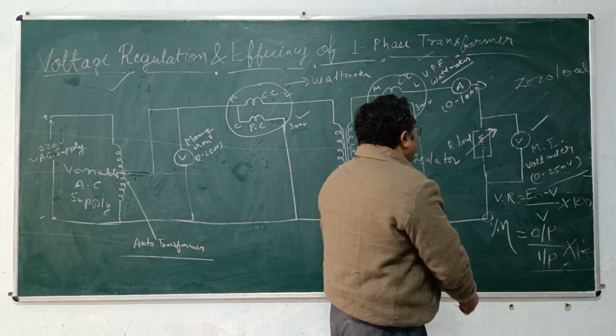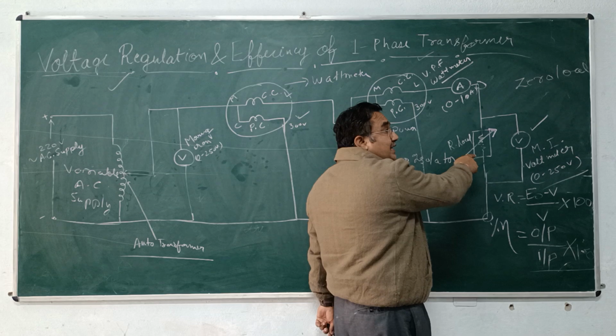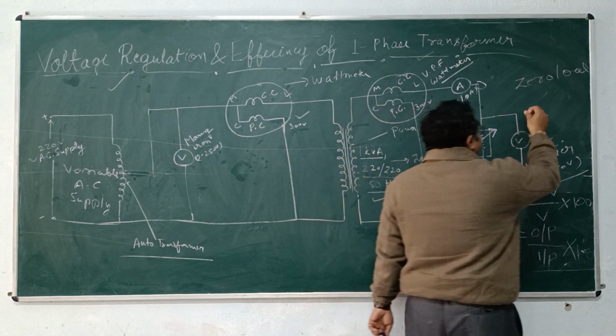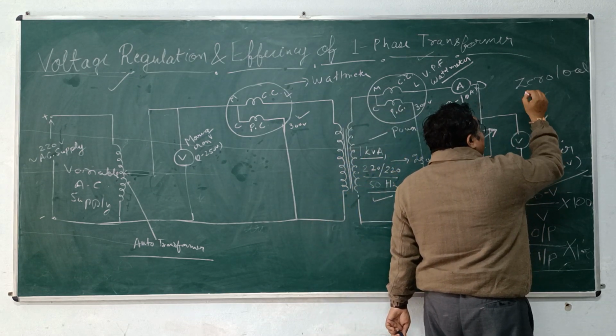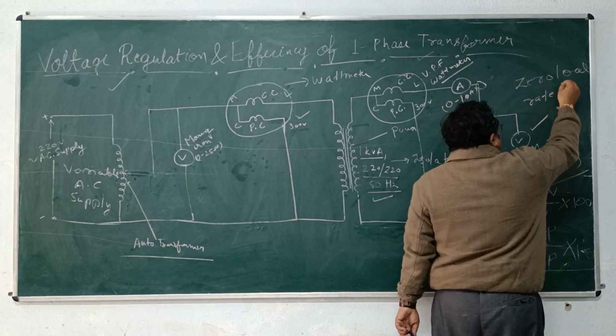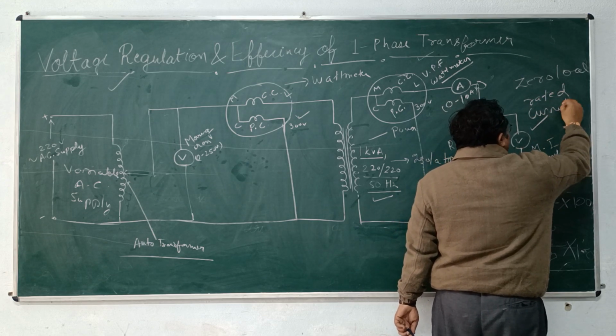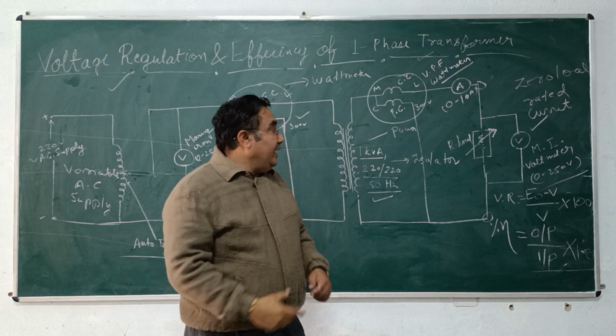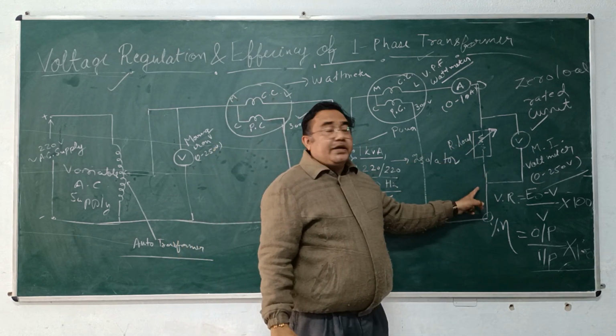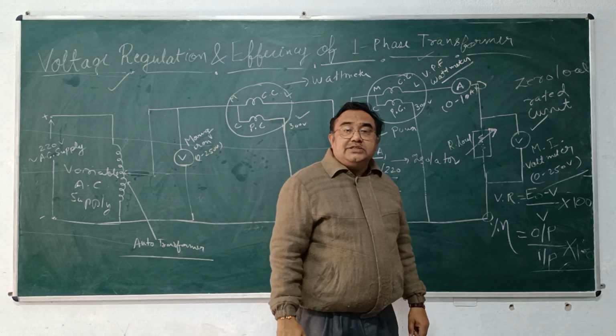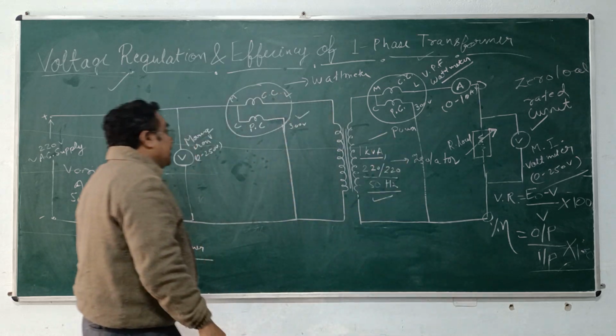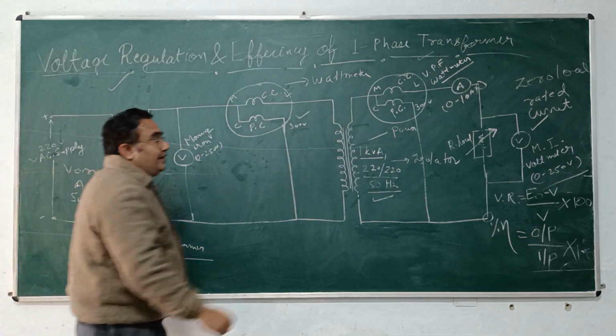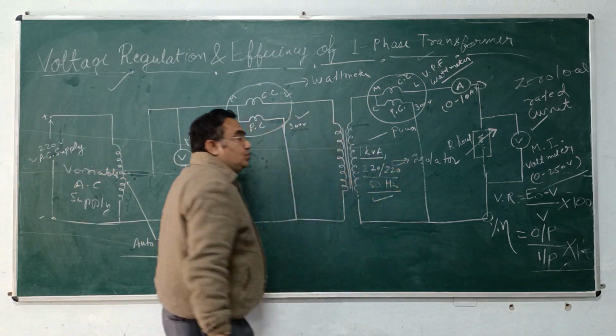Now you connect a load of the highest rating, meaning it will draw the rated current. When the transformer secondary is drawing rated current, it is at full load condition. Now, how to find out the rated current on the secondary side? For example, the maximum voltage on the secondary side is 220 volts.